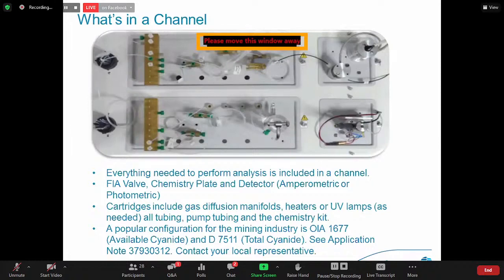And here is just a blown up view of an entire channel. So everything you need is included here: the valve, the cartridge, the detector. They include the gas diffusion modules, heaters, UV lamps, everything that's needed to perform the analysis in this one kit. Very popular configurations for the instrument in the mining industry are OIA 1677 available cyanide and 7511 total cyanide, and there is an application note available for that. So you can put both of those in the same instrument.